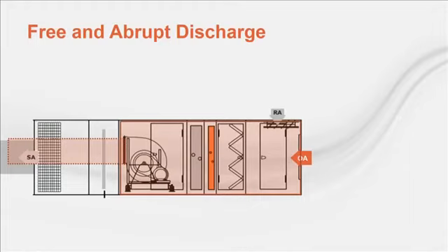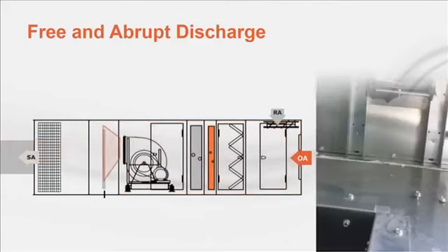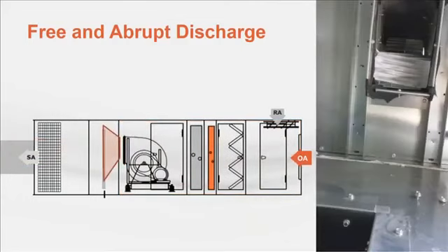A housed fan is designed for and tested with a duct connection that's about the same size as the fan discharge. If the duct isn't present, the fan performance will deviate significantly from the AMCA 210 test. Any pressure measurement taken downstream of the fan won't include this effect. This loss can be significant, as high as 1 inch in some cases.